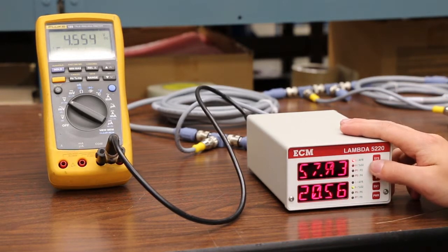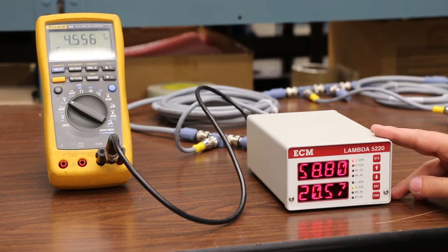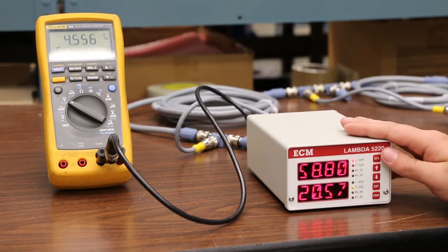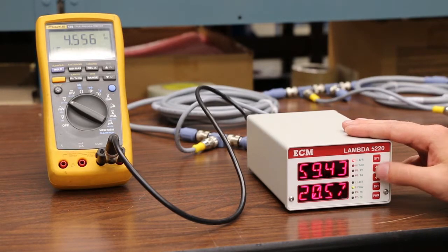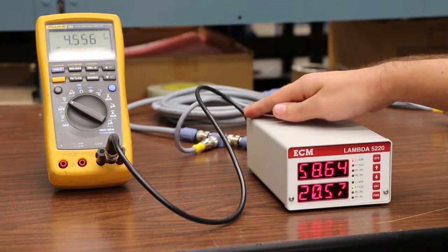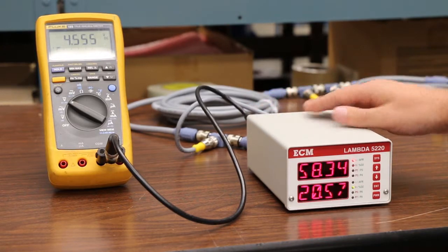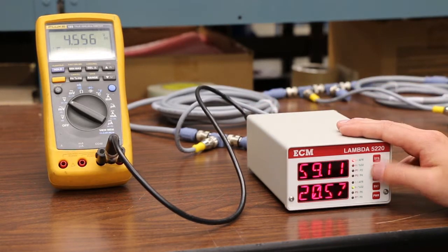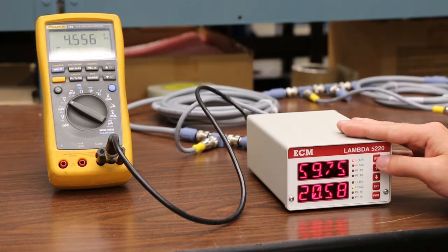To further set up the analog outputs to determine if you're getting good readings to your data acquisition system, there's also a test mode which can output 1 volt or 4 volts on all of the analog outputs to determine if the data acquisition system is reading the analog output correctly.